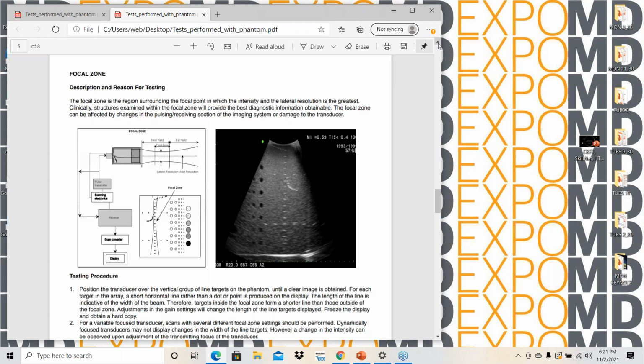So we're looking here, and the whole test is about, as you adjust the focal zone, are you seeing improvement in the image? Where you expect to see the improvement? You can add multiple focal zones, so you can have multiple regions you're looking at if you have a larger area of concern. So this tells you how to do it again, but we'll show you how to adjust the focal zones. Some of them have bars. Some of them have arrows.